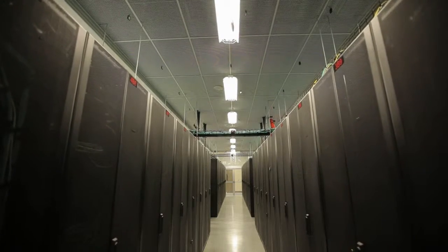A significant part of our overall efficiency and design of the data center is utilization of hot aisle containment. Our data centers typically don't have raised floor, and we use hot aisle containment to be able to raise the temperature that we bring in the data center. So in using these efficient technologies, you can extend the amount of time that you don't have to use refrigeration by raising the temperature that's being discharged from the unit. So instead of having to discharge temperatures that are in the 50s, we can discharge temperatures that are in the 70s. And so obviously we're able to economize for a longer period of time. So we use hot aisle containment to achieve that.